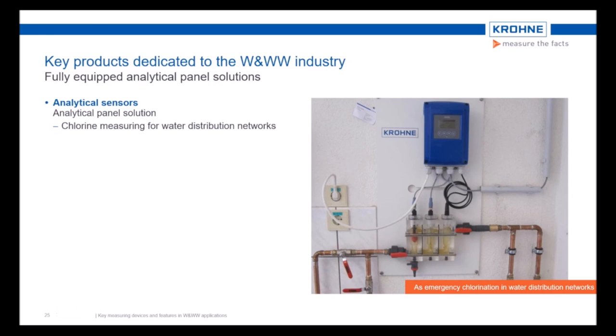As an example, we have 0.3 milligrams per liter as limit value for free chlorine at the waterworks outlet in Germany. In the US, it is much higher than in Germany. There we have 4 ppm, which means 4 milligrams per liter, and in Canada it seems to be a limit of 2 milligrams per liter. Anyway, the operators of such water distribution networks need to measure this free chlorine parameter to meet the regulations. Therefore, such analytical panel solutions, where all required sensors, even the pH sensor, electronics and even the control valves are pre-installed, are more than welcome to be installed in such emergency chlorination applications.